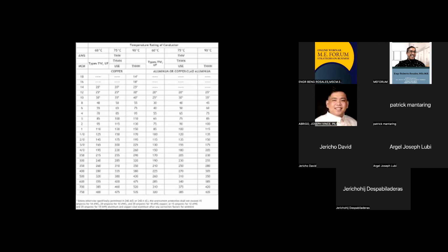Okay? So, yeah. Sorry, I got lost again. Okay. The left side is in AWG, also known as American wire gauge. Now, you can see the sizes: 18, 14, 12, 10, 8, 4. In the Philippines, they only know 12 and 14. The 12 in the English system is actually 3.5 square mm, while the 10 is 5.5, and so on and so forth. If you want the actual metric measurements, I have a table here on my desk.